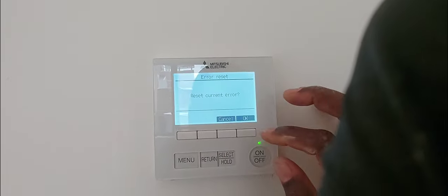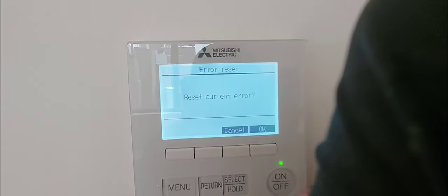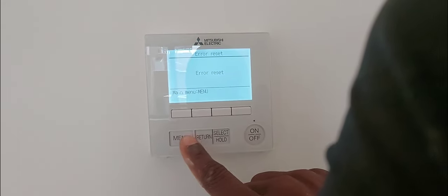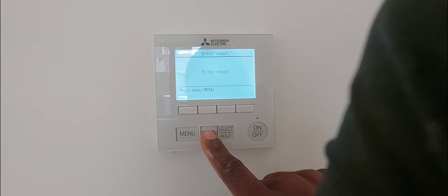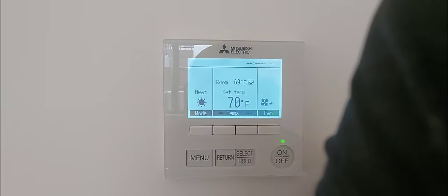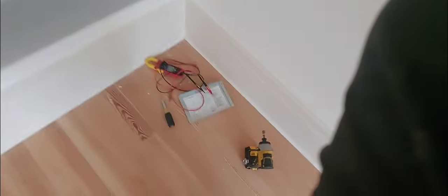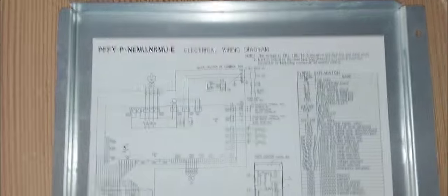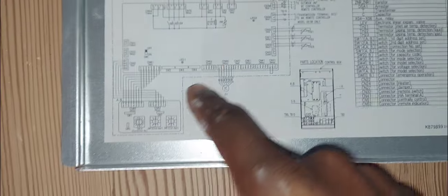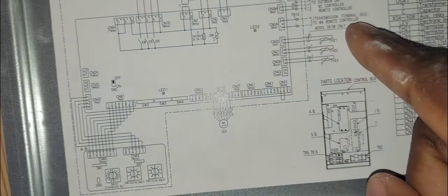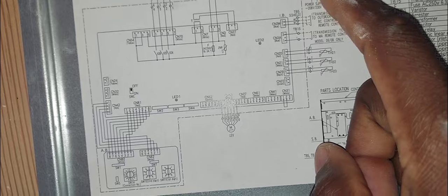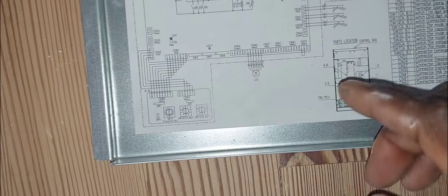I'm going to reset this error code, hit okay, then I'm going to go back to return error reset main menu return, and I'm going to turn it on again. Being that you have no DC volts on your Mnet, this error is going to come back. That's your address board, right here is your Mnet.